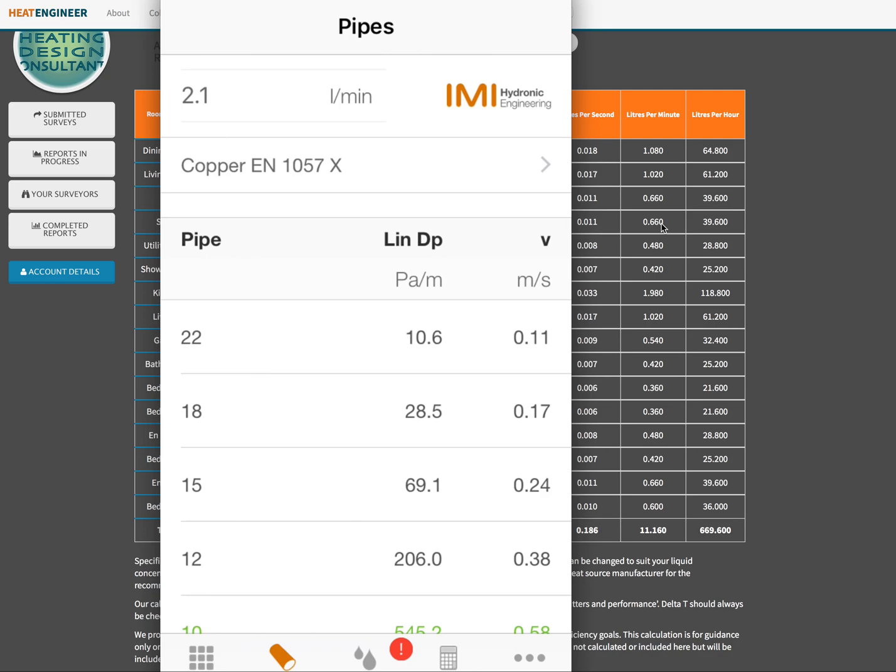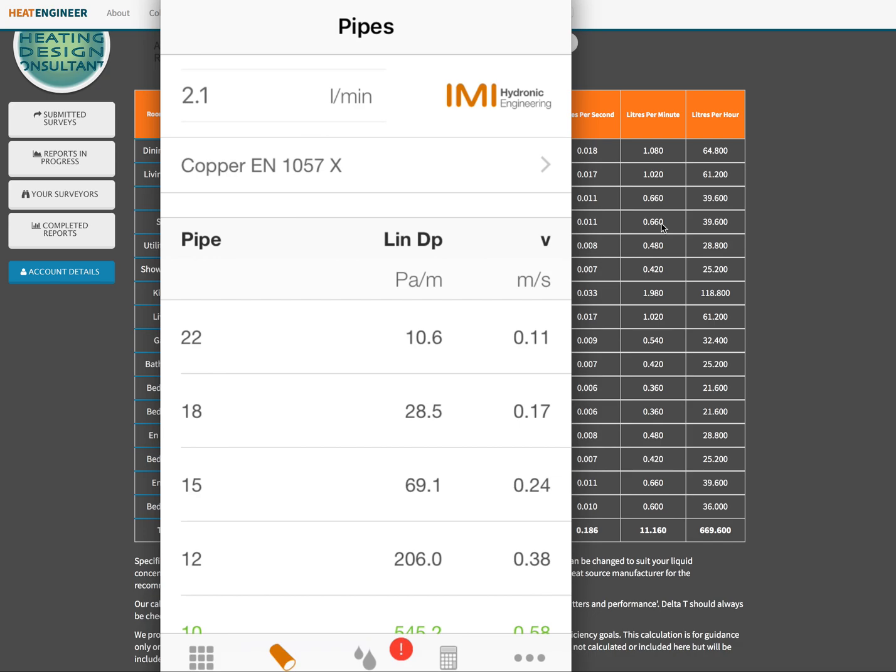Now the CIBSE guide states quite clearly that water velocities, in other words how fast water is moving through pipe work, should only be between 0.9 meters per second and 1.5 meters per second. And the reason that this is, is that to keep velocity noise down low. Anything over 1.5 and you will get velocity noise and possibly component erosion or pipe erosion. The other thing is that if it's too low, so if it's underneath 0.9, the water is not running fast enough and this is what causes sludge buildup and residue buildup within pipe work and radiators and underfloor heating circuits. This is a big problem and it's a big industry of power flushing to try and clear this problem out of the way.